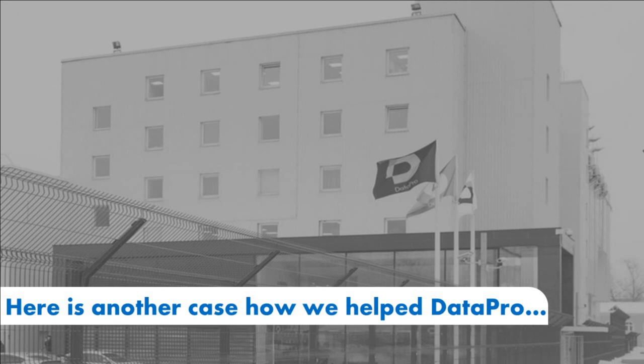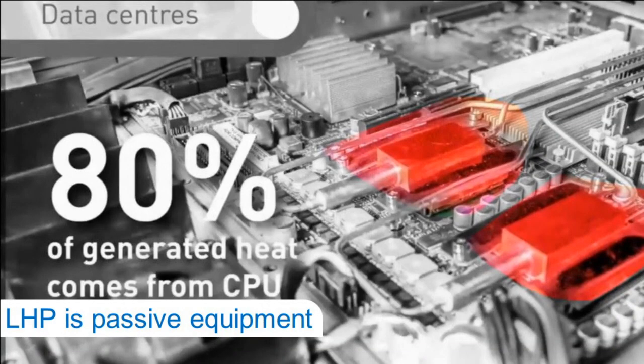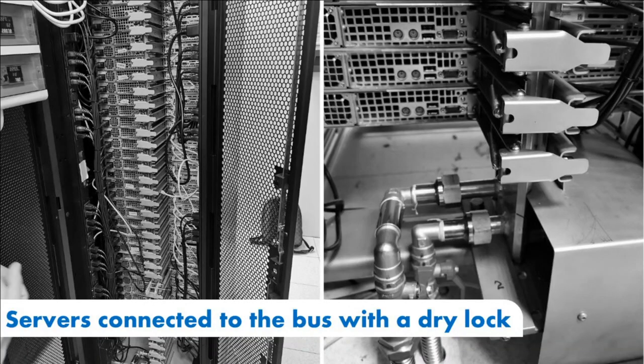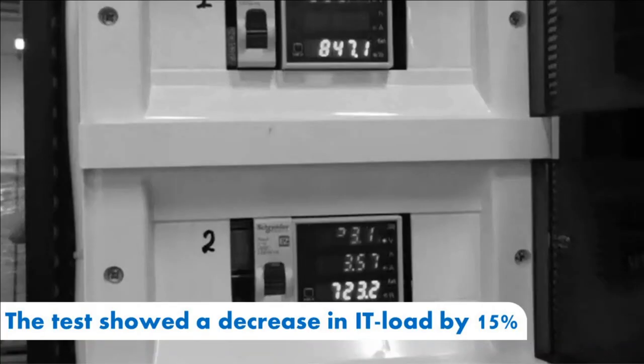Our other client, a commercial data center in Moscow, already used air-air systems, direct expansion systems, and water-based systems, and was looking for the most effective solution for server cooling. And he decided to apply a solution on loop heat pipes, Tercon technology, with passive heat removal from server processors, and installed one rack for testing. In the rear part of the rack you can see the bus to which the dry locks of the loop heat pipes are attached. And the fluid circulates in the bus, which removes heat. Moreover, this bus has two inputs and outputs, which provides redundancy. At the top you see the energy consumption of classic servers, and below the energy consumption of the servers equipped with LHP Tercon. Real-world testing showed a 15% reduction in load.